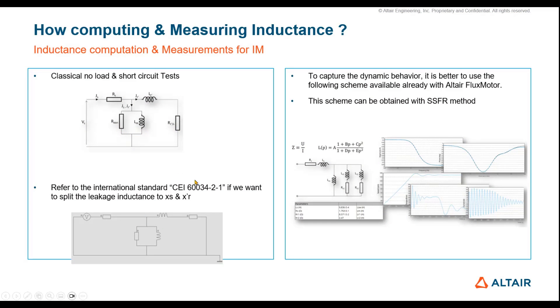For the induction machine, the well-known single-phase equivalent scheme is obtained from short circuit and open circuit tests, and is given automatically by Flux Motor. If we want to split the leakage inductances between rotor and stator, we need to refer to the international standard describing how to split these two inductances. The SSFR method is also applied in Flux Motor and gives this scheme automatically — it is more adapted to capture the dynamic behavior, while the single-phase equivalent is more adapted to steady-state analysis.